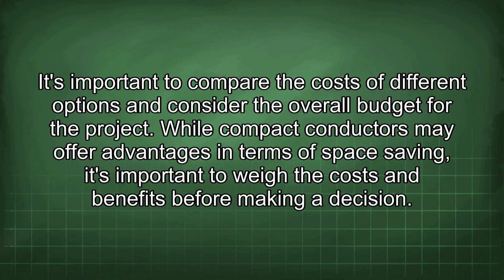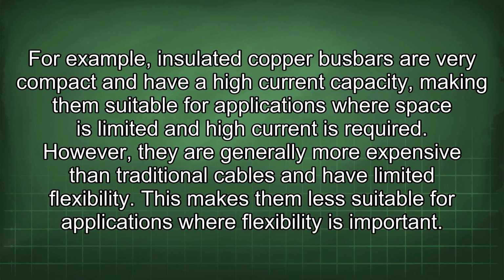For example, insulated copper busbars are very compact and have a high current capacity, making them suitable for applications where space is limited and high current is required. However, they are generally more expensive than traditional cables and have limited flexibility. This makes them less suitable for applications where flexibility is important.